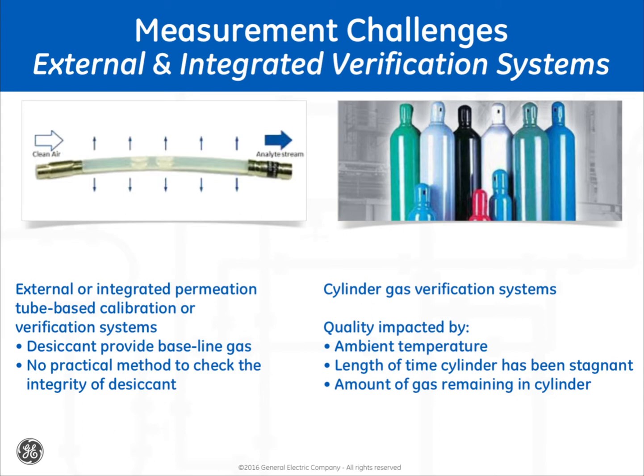Any moisture measurement technology may come with external or integrated calibration and/or verification devices with their moisture measurement system. These may include permeation tube or cylinder gas techniques. Permeation tube systems employ a desiccant to remove the moisture from the process gas or other carrier gas, resulting in a zero baseline. And then the permeation tube adds moisture to this gas to set a calibration point. There is no practical method to check the integrity of the desiccant. The system must also maintain proper control of flow and temperature.